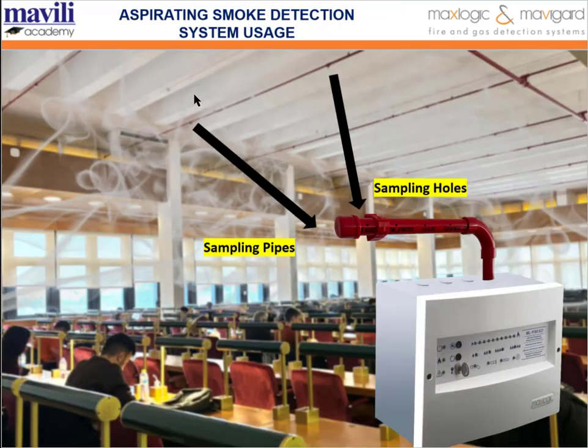Yes, the most important one is the aspirating smoke detection system. We can see the system usage here. There is a pipe and sampling pipes, and on it sampling holes. So what is it? In these systems, ambient air is continuously drawn through a special pipe network and analyzed by high sensitivity laser detectors. The system actively draws in air, analyzes smoke particles, detects very low levels of smoke, and generates an early alarm. Therefore it is also defined as a very early warning system.